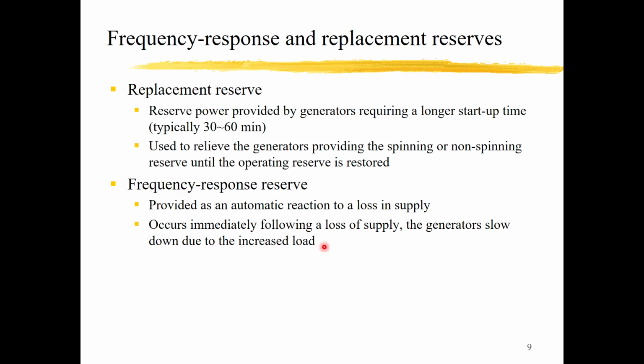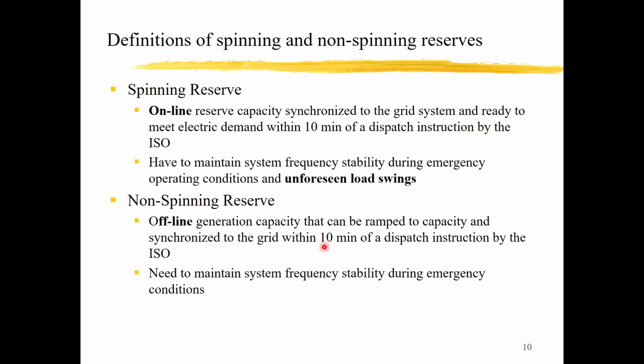As I said, if the load increases and the supply is not enough, then the generators will be slowed down, so the frequency will become smaller. Then the frequency response reserve has to be cut in to supply the power to restore the frequency. Okay, this is the so-called frequency response reserve.